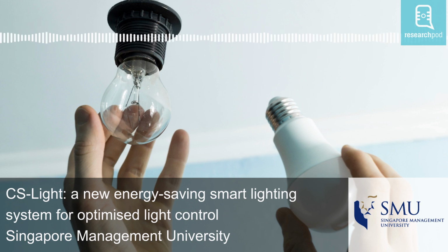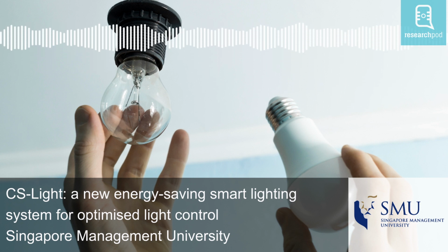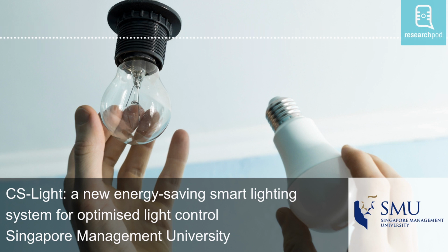These estimates and values associated with the level of human occupancy, as well as the brightness of LED luminaires, were fed into the Smart Light Optimizer software. The software calculates the optimal level of lighting for LED luminaires. Here, optimal refers to the desire that the cumulative intensity of the LEDs should be enough to ensure that all occupied areas or tables were comfortably lit, and no higher so as not to waste energy, while unoccupied areas could be darker. These settings were then provided to the Smart Light Controller software, which adjusts the LED luminaire settings to provide the optimal lighting level for each workspace zone.